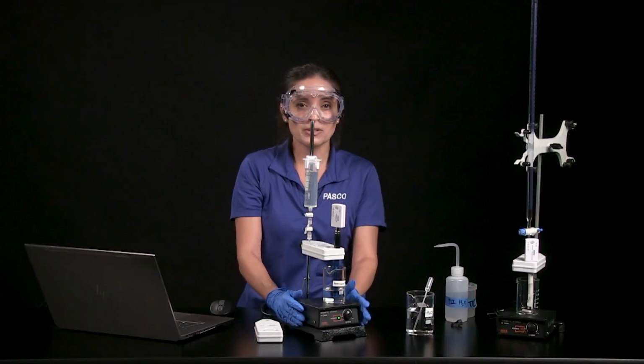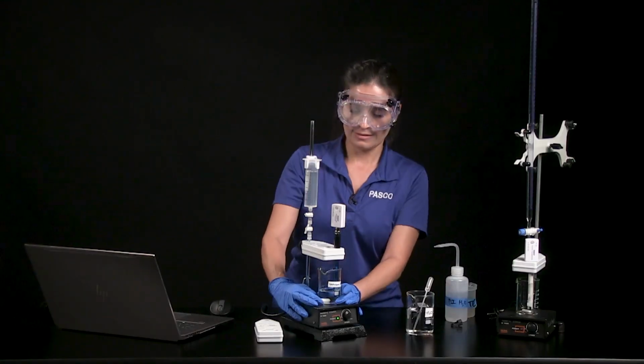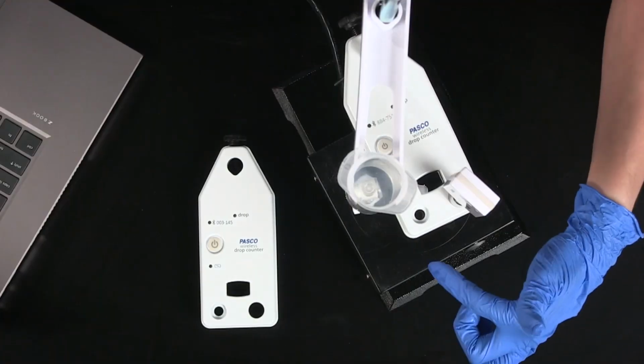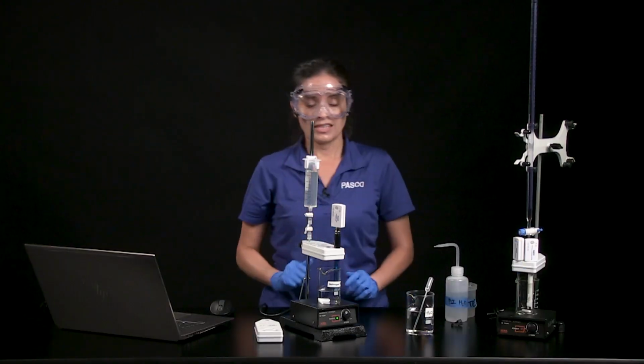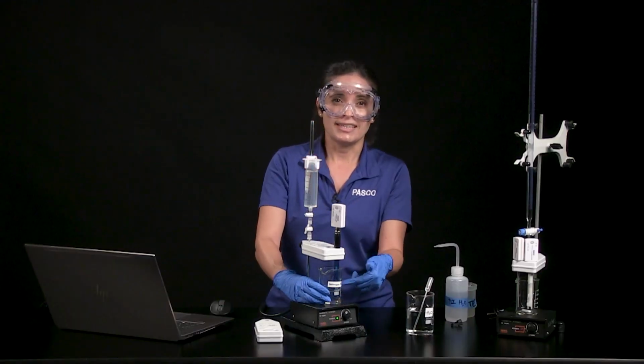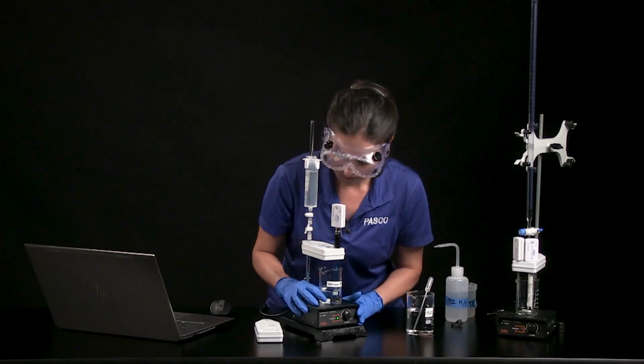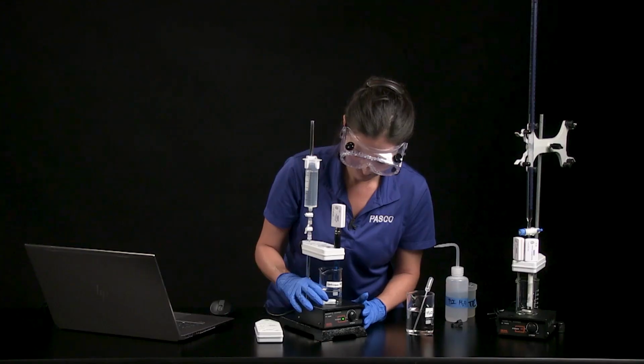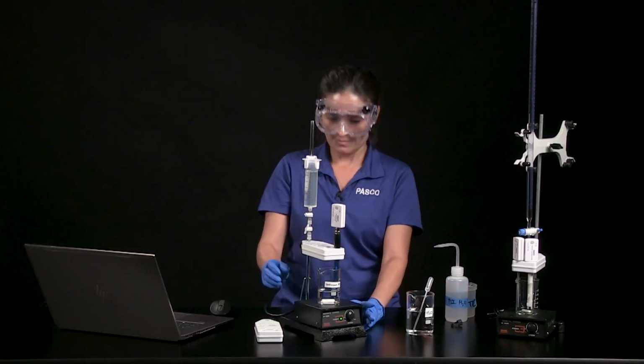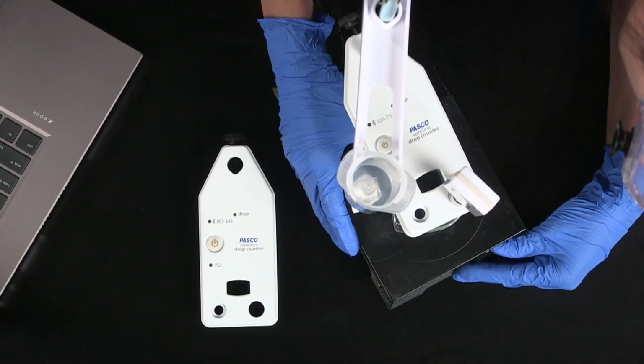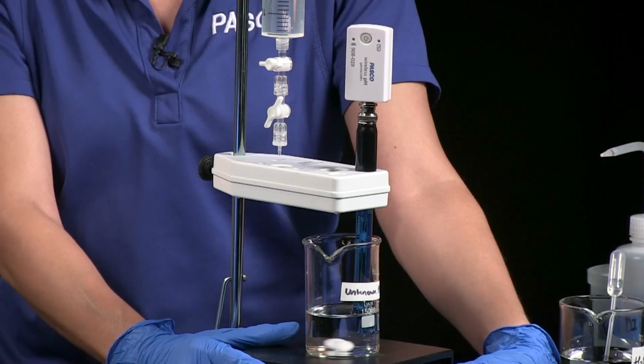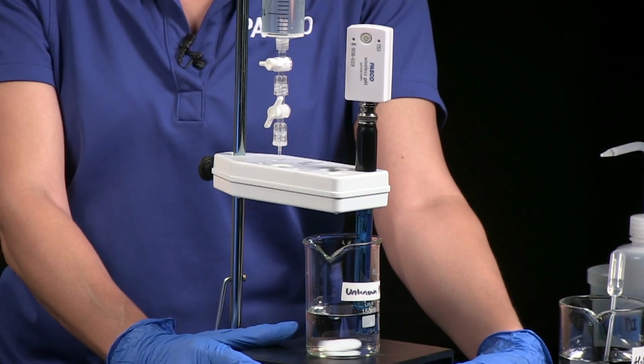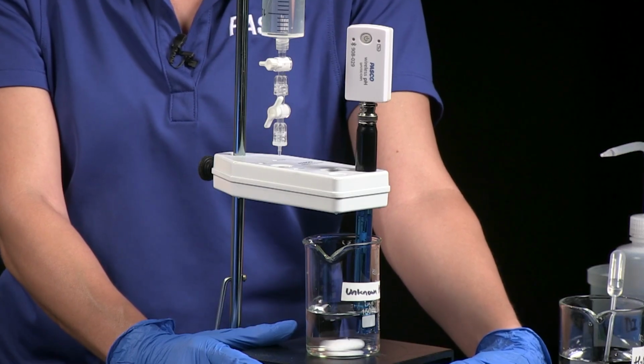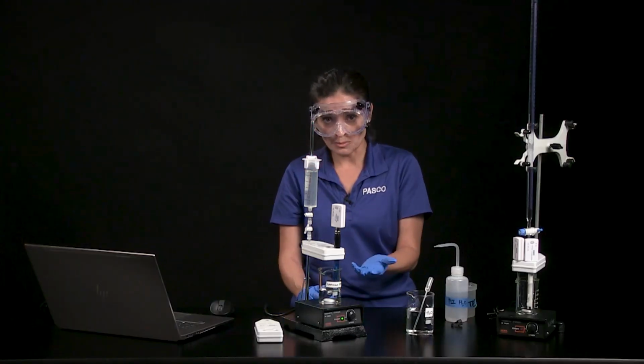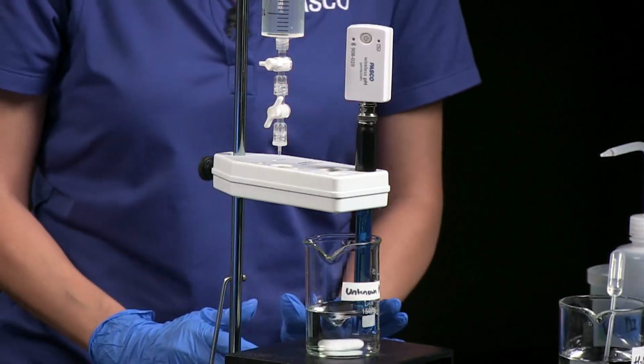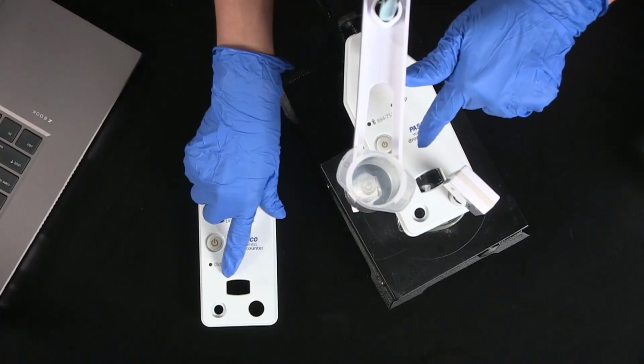Now arrange the system so the drop counter window is completely over the beaker. If desired, you can add a temperature probe to the second hole on the opposite corner. Now make adjustments so the bar magnet will not strike the pH probe, and at the same time look through the drop counter window to make sure the beaker is still below it. Turn on the stirrer to a slow speed, and then speed up slowly until you reach a speed where you achieve a vortex with no splashing. Add more distilled water if needed to completely cover the glass bulb, and that looks okay. Check your setup one last time and try to aim the center of the vortex directly below the drop counter window.